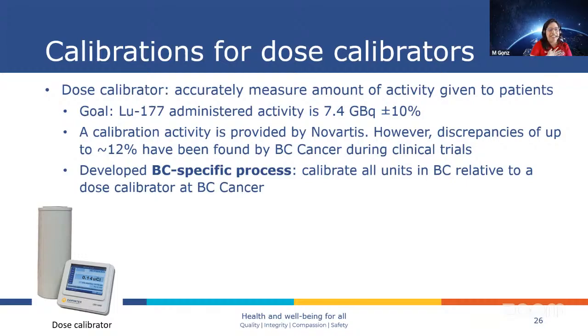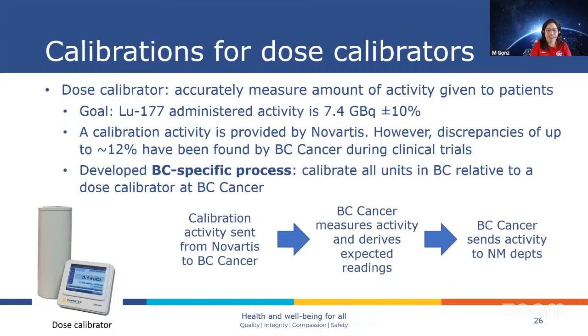So what we decided with the physicists at BC Cancer was that we were going to develop our own process to calibrate those calibrators in BC. So instead of using the doses and the values that were coming from Novartis, BC Cancer was going to receive those calibration doses, confirm what that value is, and then send it back to the nuke med department. So we changed it. So we developed this specific process for us. So it involved BC Cancer receiving the doses and sending them to the nuke med departments.